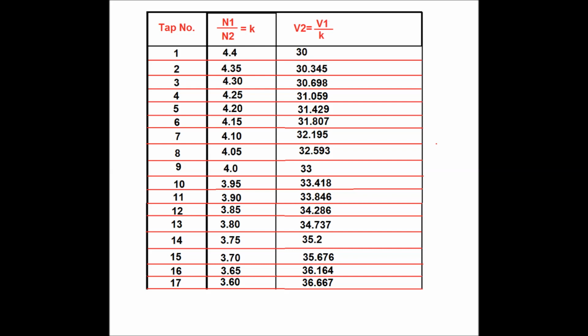So in this table, how the LV side voltage can be regulated for different tap positions has been shown. At tap position 1, since the maximum tap winding is selected for HV side winding, the N1 by N2 ratio is maximum, that is 4.4. So at tap position 1, the LV side voltage would be minimum, that is 30 kV. Again, by increasing the tap number, the LV side voltage shall be increased to 30.345 kV at tap position 2. At tap position 3, the voltage shall be 30.698 kV, and so on. At tap position 9, at nominal tap, the voltage shall be 33 kV, and at tap position 10, the voltage shall be 33.418 kV, and so on.